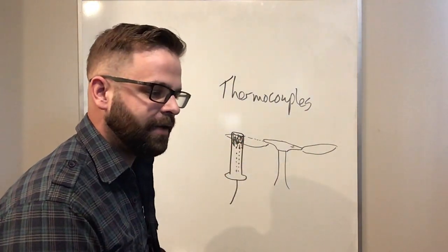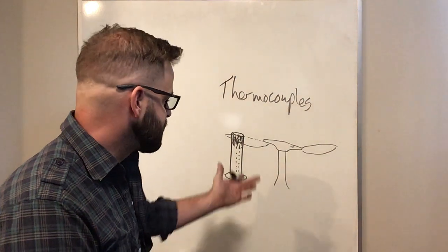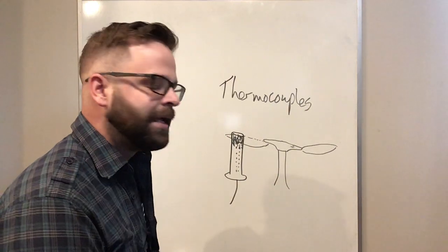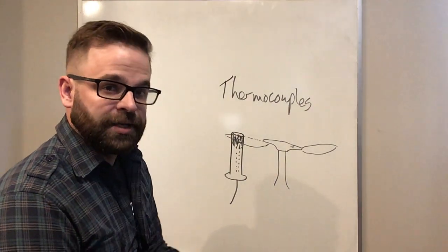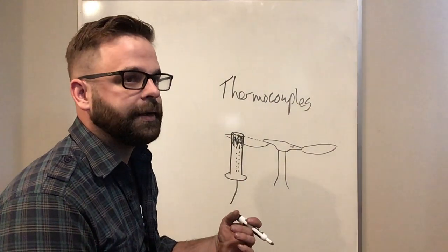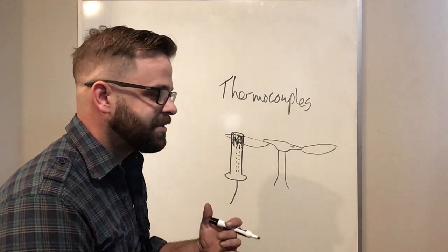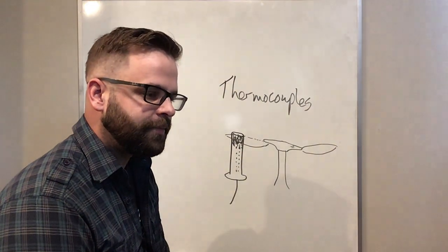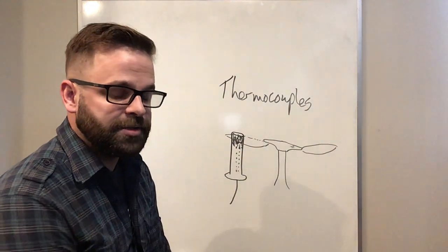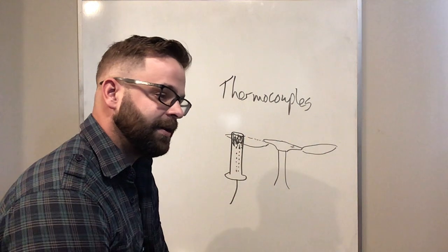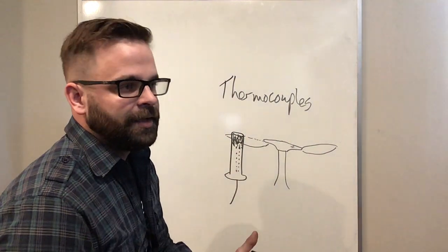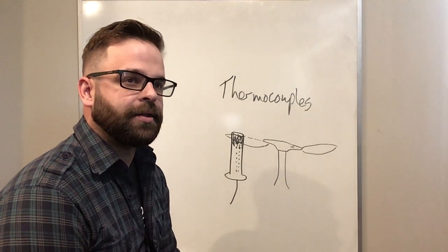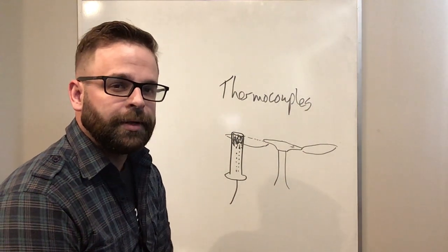So what you end up having to do is to go in and clean that soot off of that thermocouple. And one of the best ways to do it is with a little bit of sandcloth or sandpaper, or sometimes even steel wool. Restaurants will have this happen a lot with their deep fryers. I've been in to do stuff like that, and something that's on hand, because you don't always have sandcloth on you unless you're a plumber.